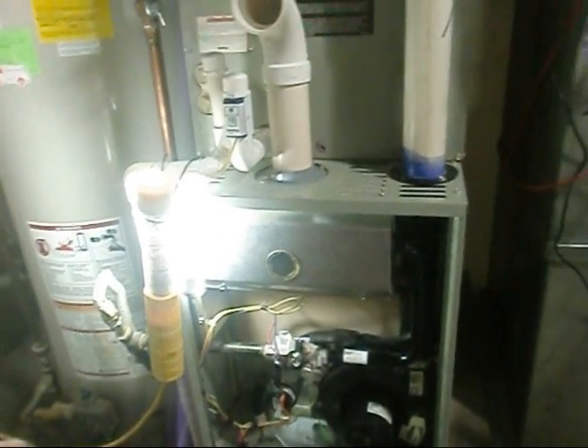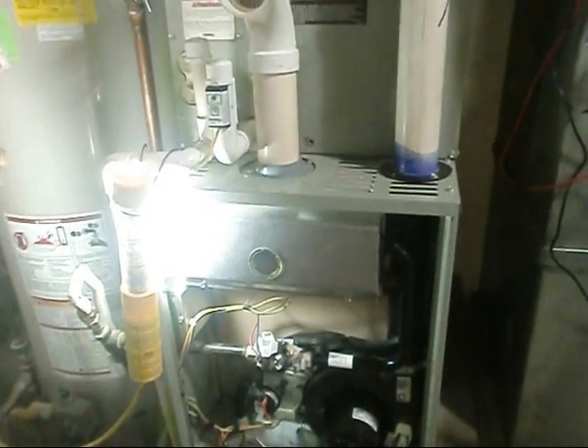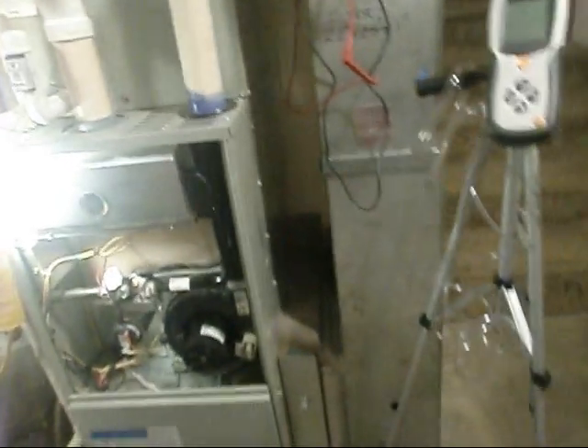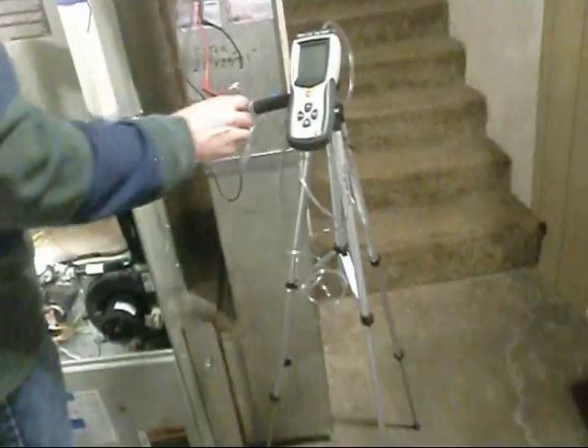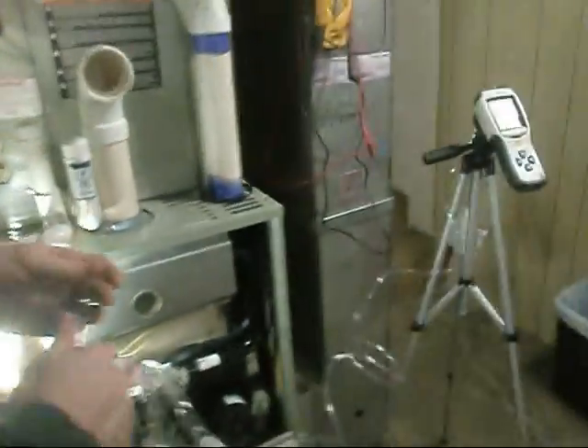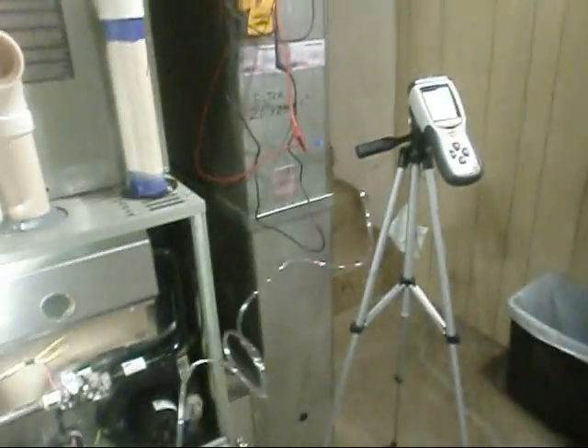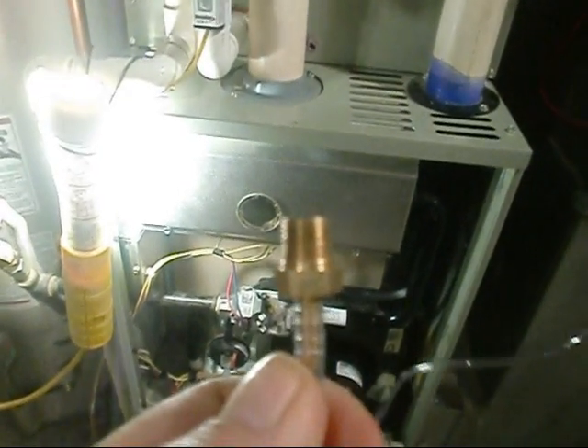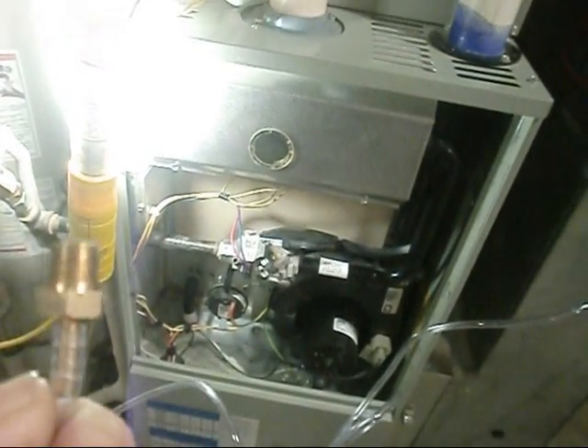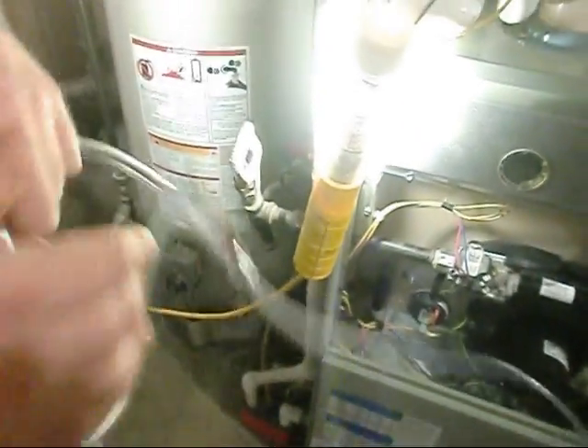Did you get it out? Yeah, it's out. Now set that somewhere it won't get away from us, put it up on the water heater. I've got you set up with the manometer here, changed out some hoses. Most gas valves take this fitting right here, but my particular model doesn't, and I don't have that size. So we'll just take that hose and go right over the tip on there.